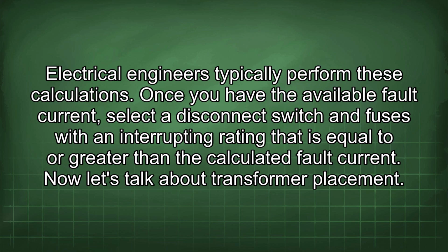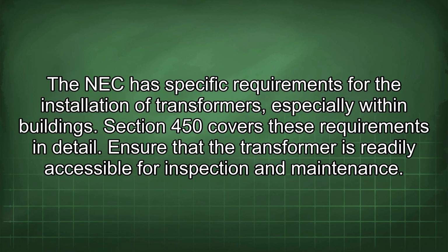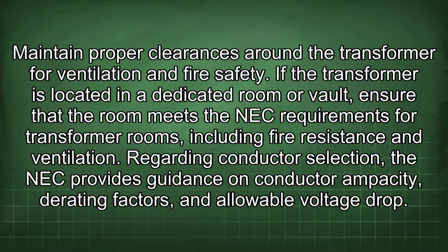Now let's talk about transformer placement. The NEC has specific requirements for the installation of transformers, especially within buildings. Section 450 covers these requirements in detail. Ensure that the transformer is readily accessible for inspection and maintenance. Maintain proper clearances around the transformer for ventilation and fire safety. If the transformer is located in a dedicated room or vault, ensure that the room meets the NEC requirements for transformer rooms, including fire resistance and ventilation.